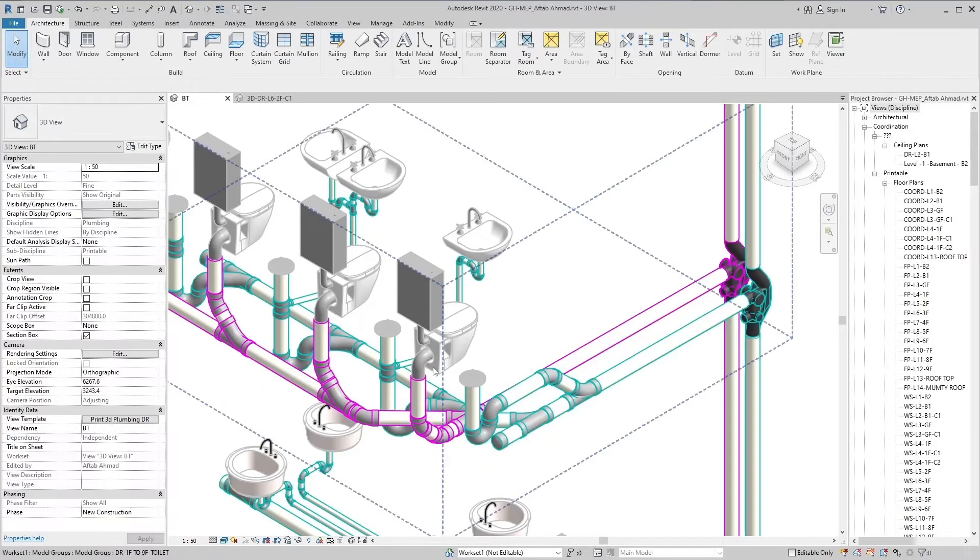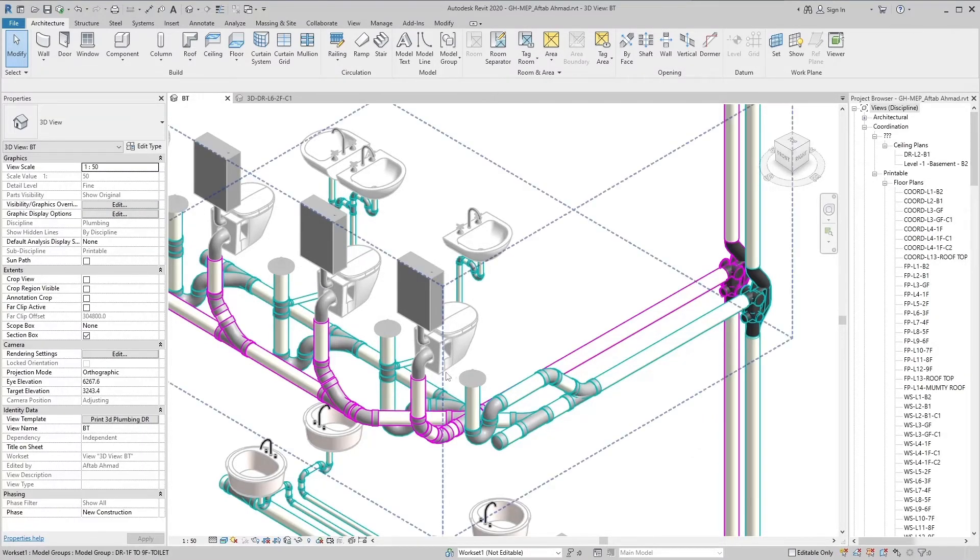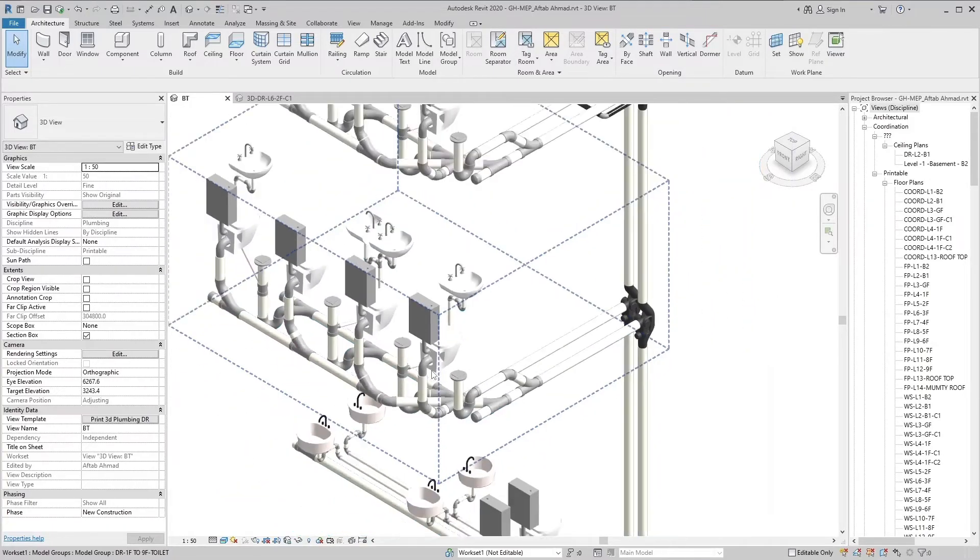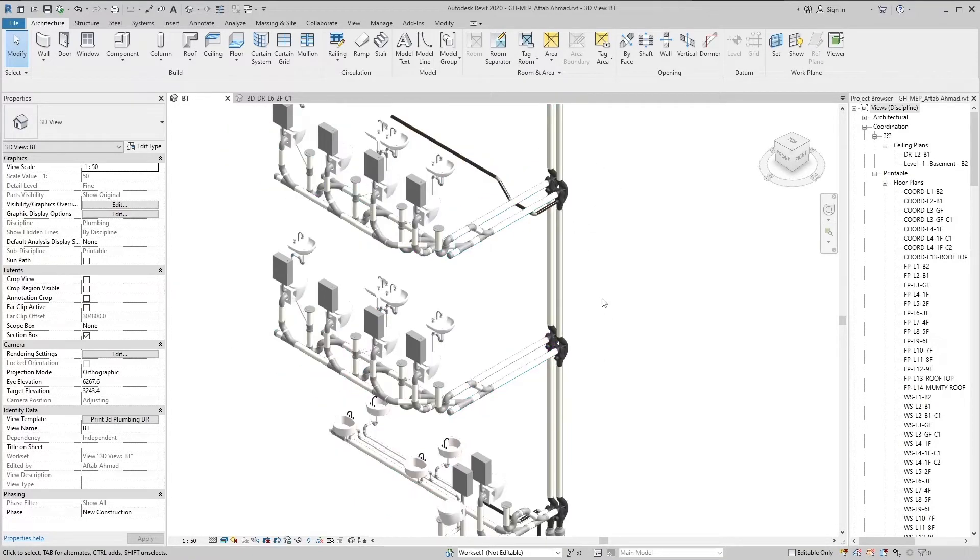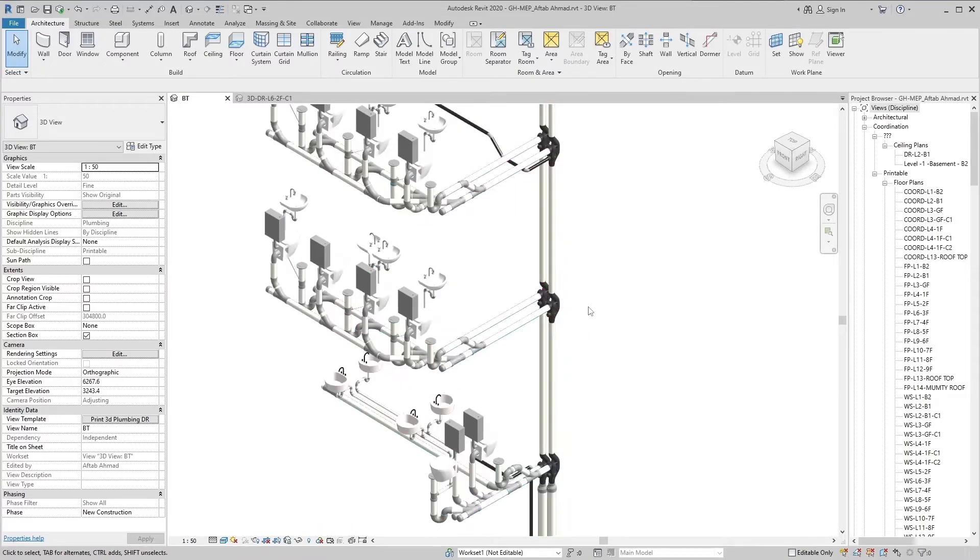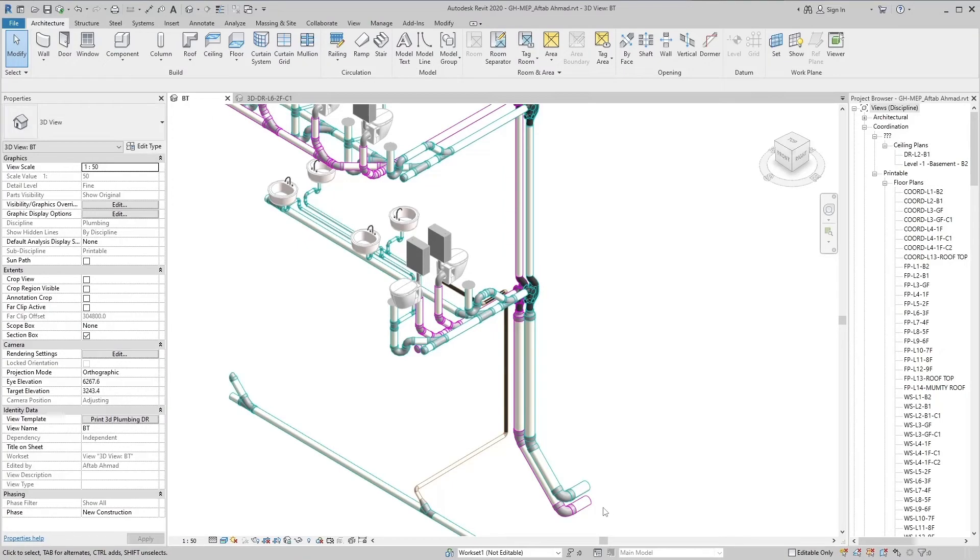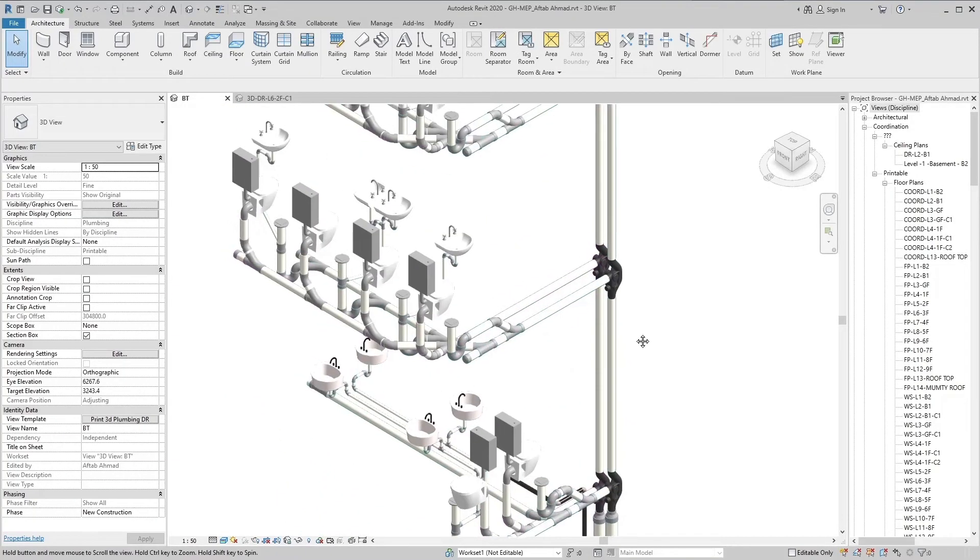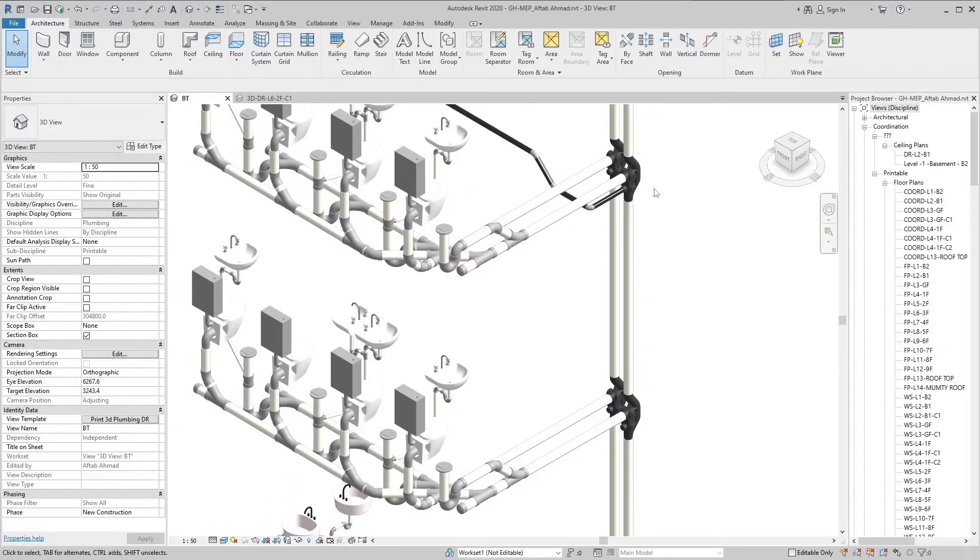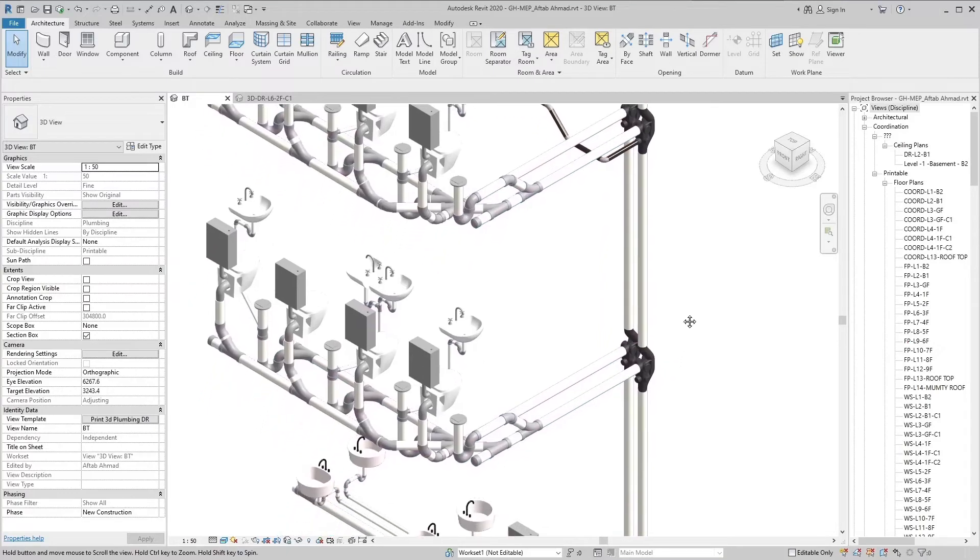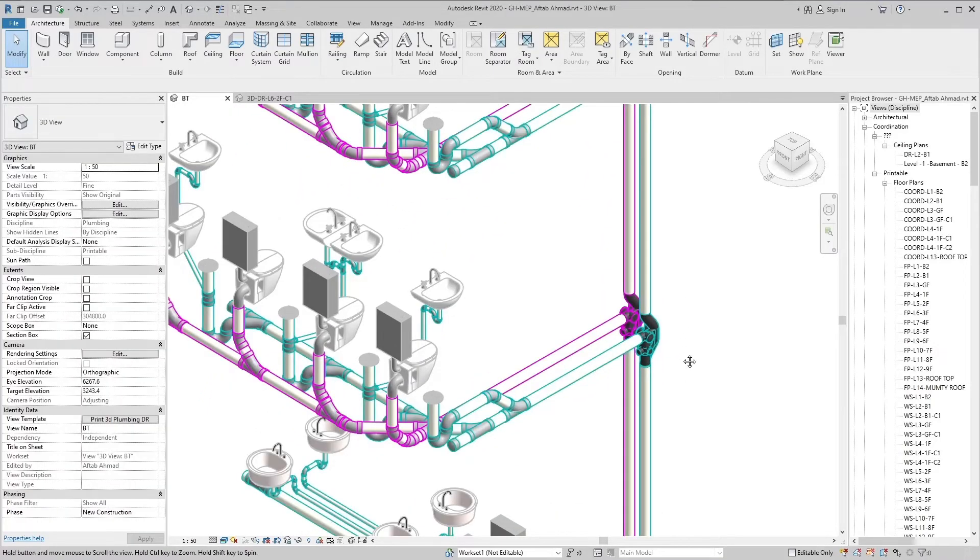In 100 to 150 diameter pipe, terminal velocity is reached within 1.5 meters to 3 meters from the discharge. Velocity breakers shall be required in soil stacks in buildings more than 30 stories above grade to impede the velocity of the waste, otherwise it hits the bottom pipe of the drainage stack and can damage it. The velocity breaker should be installed at a maximum of 15 meters. I will show you in a project how to install velocity breaker.